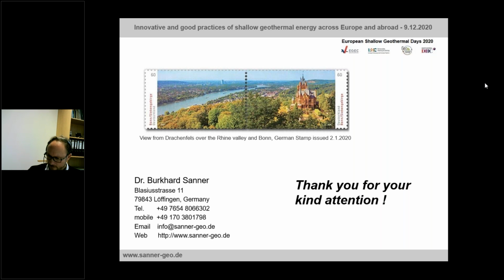This is to make sure that the flow of the warm water always goes away from cooling in the vicinity of the neighboring open loop system. And by doing that, we can also optimize the temperature field around the winter wells and summer wells. So the temperature is always a little bit lower in the wells where we extract in summer, and a little bit higher where we extract in winter time.